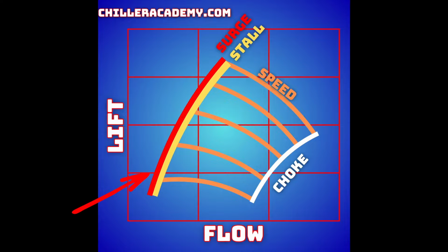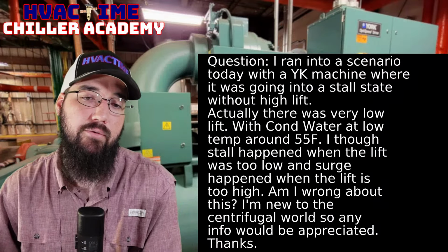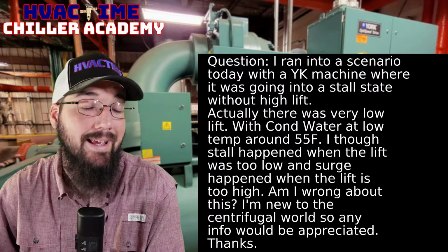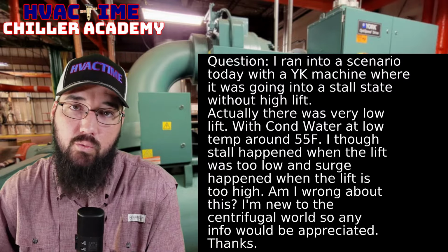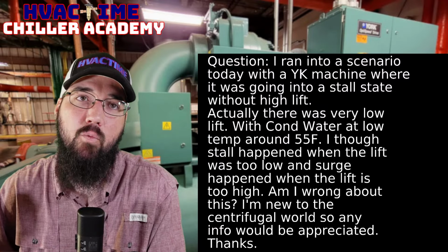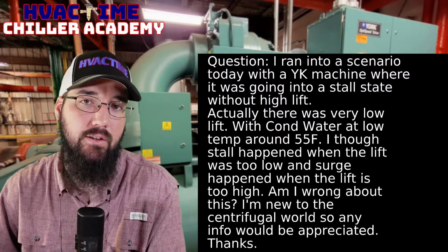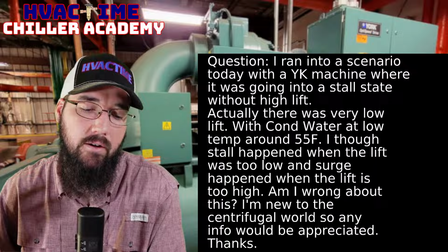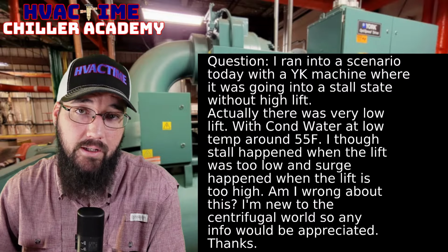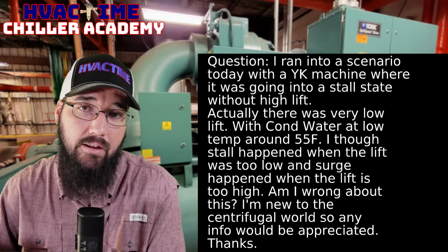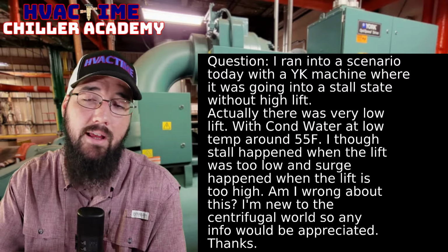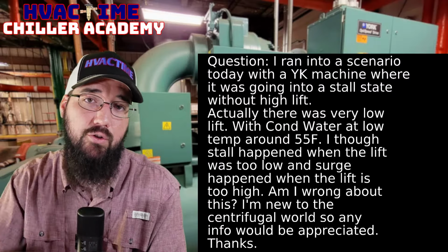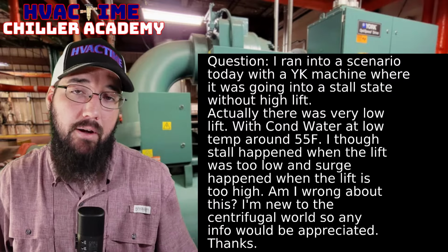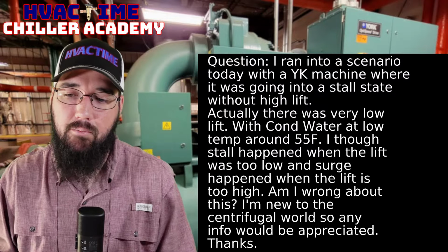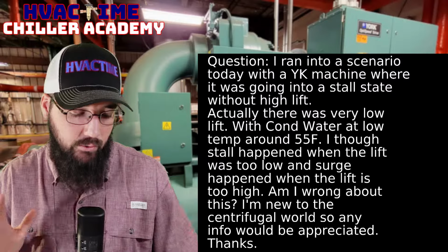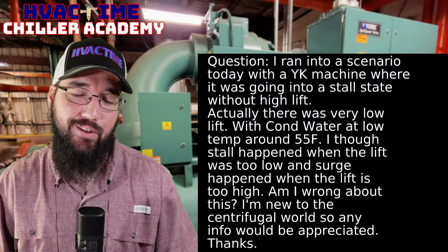It's still possible. So from your point of view, we have low lift but I'm still surging, it depends on the conditions. It depends on refrigerant charge, it depends on what your evaporator liquid level is maintaining at, which you can see in the sight glass. It depends on the condition of your impeller. If your impeller has any damage, it's going to struggle maintaining lift as well. The only way to answer if the impeller has damage is to open up the compressor. That's maybe a bit overkill given our circumstances, right? So just bear that in mind. Let's rule out everything else first. That would be the goal there.